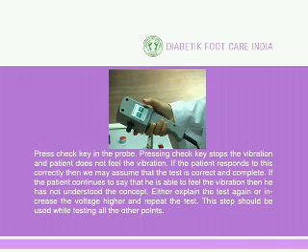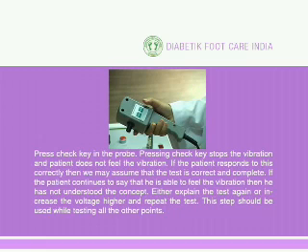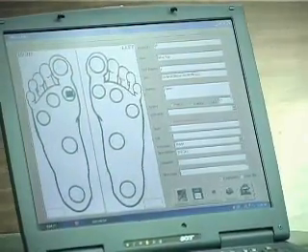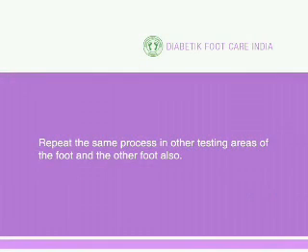If the patient continues to say they feel the vibration after the check key is pressed, they have not understood the concept. This step should be used while testing all other points. When the vibration value is reconfirmed, record the displayed reading to the PC by pressing the record button on the VPT probe. Reduce the voltage and repeat the same process in other testing areas of the foot and the other foot as well.